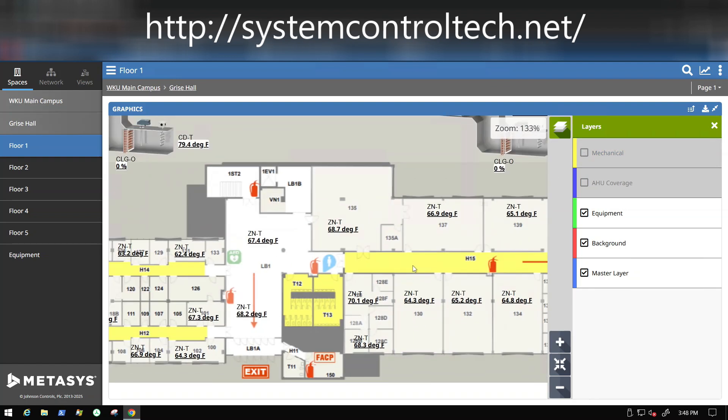Now this is just one of the ways that you can use the layers — the air handler coverage. The reason I wanted to make this video is because of an upcoming project we have for a new construction facility where there are two sets of VAVs that are going to be overlapping in their coverage. One VAV is going to be providing outside air to a group of rooms, while an additional room VAV will be doing the main temperature control for an individual room. So using the layers, we're going to be able to differentiate between the room VAV and the one providing outside air.